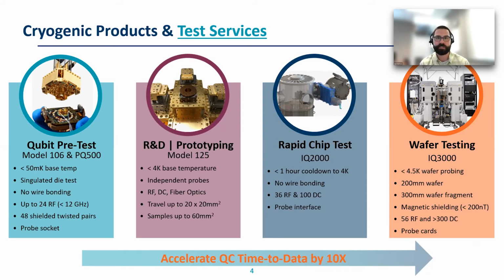One of the biggest things we're seeing is that there's still this fundamental uncertainty on what information you can obtain at 300 Kelvin versus what you can obtain at the low temperatures. A lot of customers are working through that in different ways, and it also depends upon the particular modality you're looking at. For instance, photonic probing and some of the advancements there might require the lower base temperatures, especially when you're starting to look at integrated devices, things that might have photon sources, waveguides, and detectors all in a single chip. That's something you really want to be probing at cryogenic temperatures. Whereas some of the test control or even some of the cryo CMOS stuff can be done at higher temperatures. As we go forward, systems that provide customers a lot of data are really going to advance materials development programs, as well as some of the fundamental structures that go into a quantum processing unit.